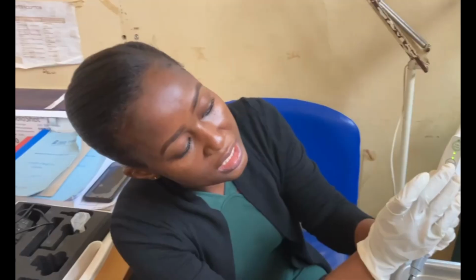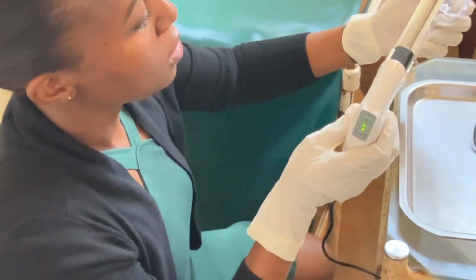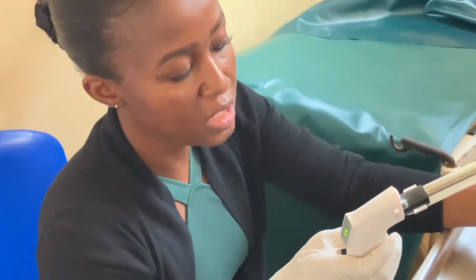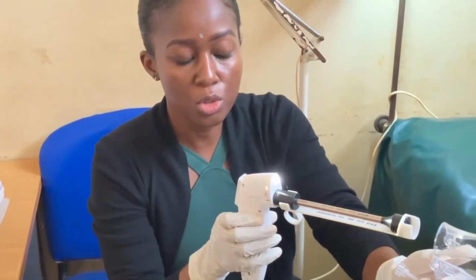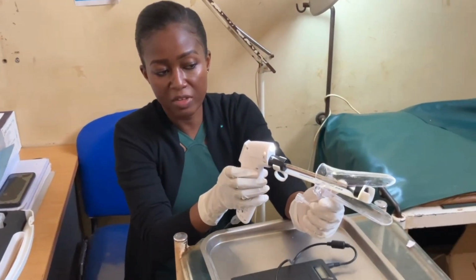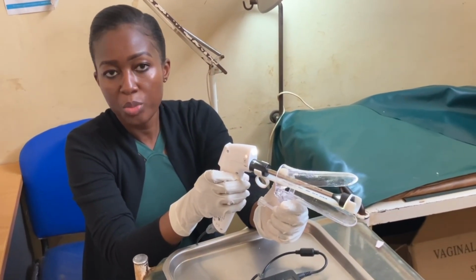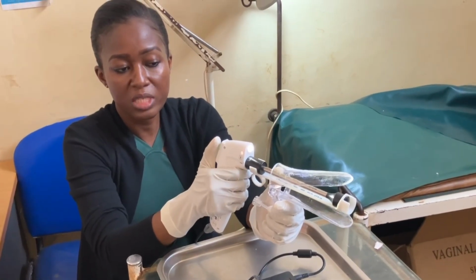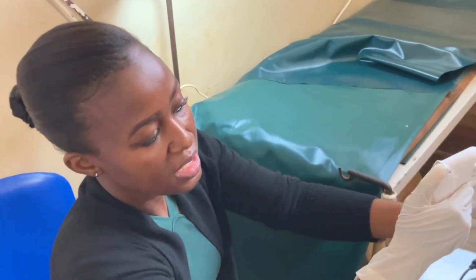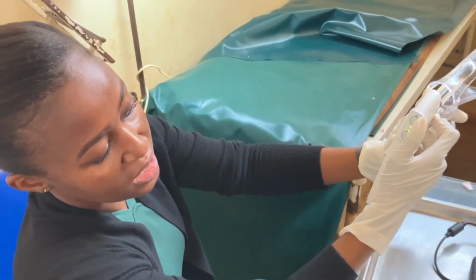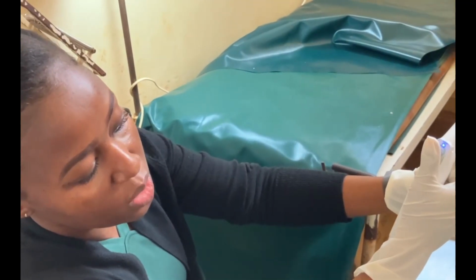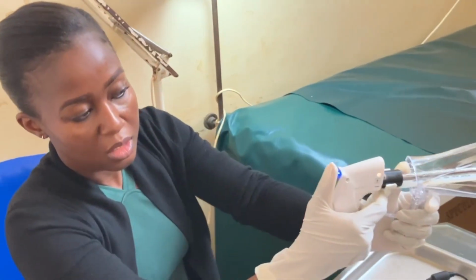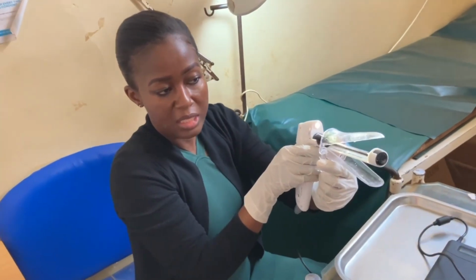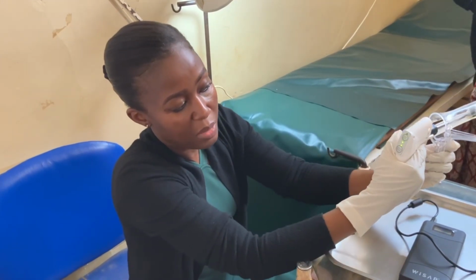Once the light stops flashing, it means that the heating is done and the probe is ready to use. For demonstration's sake, once you have your patient and your speculum is already in place, you're going to advance your probe towards the cervix and make sure that the probe is in contact with the cervix, and then you start the timer. When you start the timer, you will notice a blue light that comes on and flashes. Then you pull your slider back so that now the probe is exposed. Then you just let the timer count down.